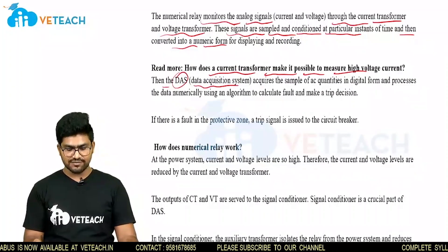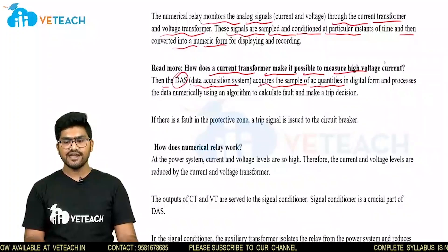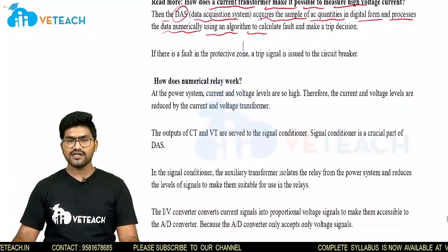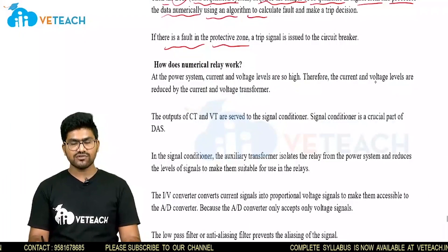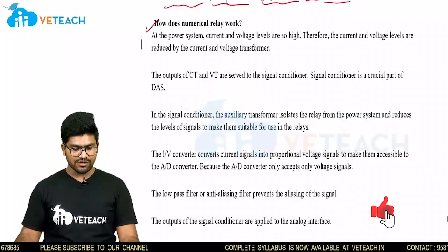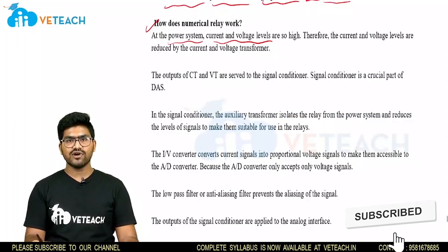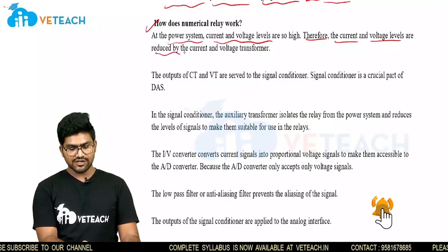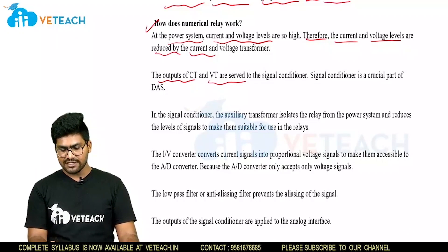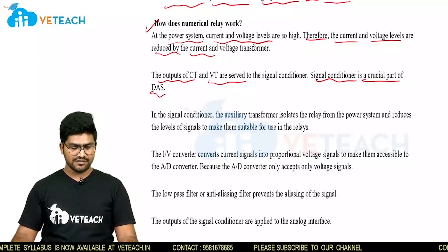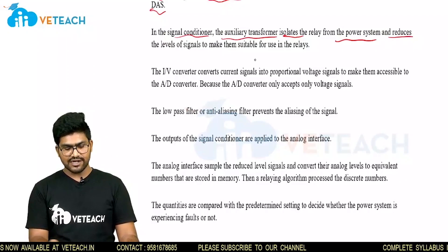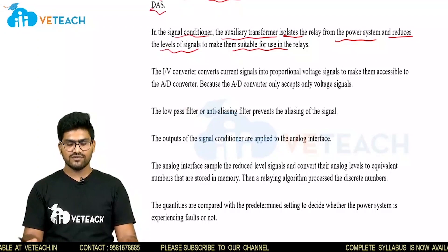A DAS, meaning data acquisition system, acquires samples of AC quantities in digital form and processes data numerically using algorithms to calculate faults and make a trip decision. If there is a fault in the protective zone, the trip signal is issued to the circuit breaker. At the power system, current and voltage levels are very high. Therefore, the current and voltage levels are reduced by current and voltage transformers. The outputs of CT and VT are served to the signal conditioner. Signal conditioning is a crucial part of the DAS. In the signal conditioner, the auxiliary transformer isolates the relay from the power system and reduces the level of signals to make them suitable for use in the relay.